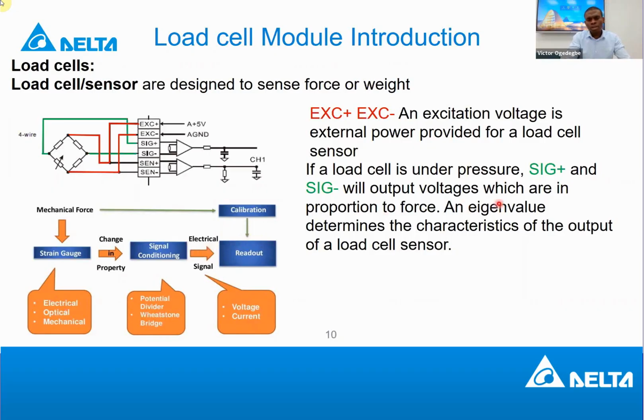The output voltage depends on the eigenvalue of the sensor. Each sensor or each load cell has a different eigenvalue, and the eigenvalue determines the characteristic output of the sensor. That's why, if you are configuring your load application, you need to choose the eigenvalue that is compatible with the sensor you are using. The sensor I showed you earlier has an eigenvalue of 1 millivolt.